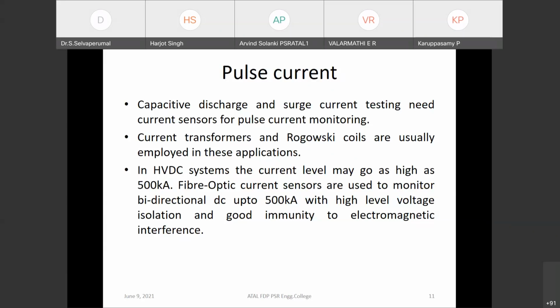In low voltage applications, shunt resistors are also used to monitor pulse current, but their use is often limited by the pulse heat dissipation represented by I square R T rating, right? A combination of Hall effect sensor and current transformer is used in designing a current probe capable of measuring both DC and AC up to 40 ampere current and a bandwidth from DC to 30 megahertz. Right? So owing to small size and high bandwidth, magnetoresistive sensors find frequent use in brushless DC motors and special machines like BLDC motor and switched reluctance motor to sense square-shaped current. Right. So next slide.